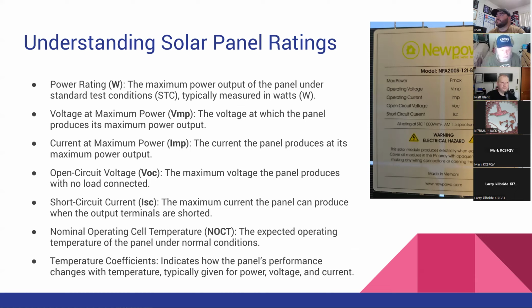If you stay 25% under your input, you should be fine - 15% is probably okay, but in some cases the open circuit voltage will actually exceed this if the panel's cold. There's more math you can do to figure that out if you want to get really optimized and have something that isn't going to change. You can do all that math, but I like to just give it a good safety margin.